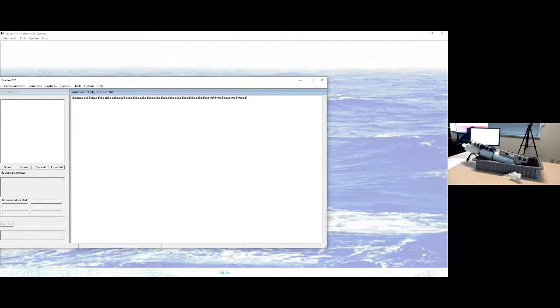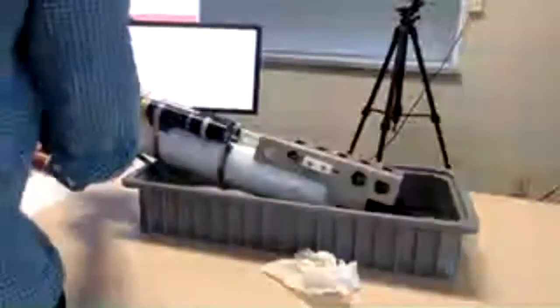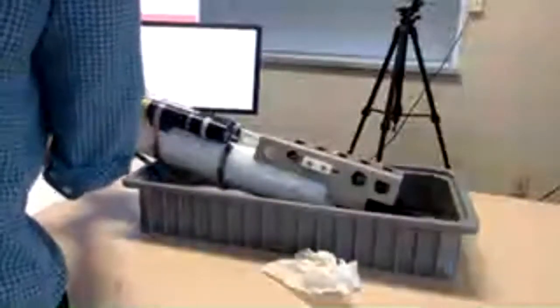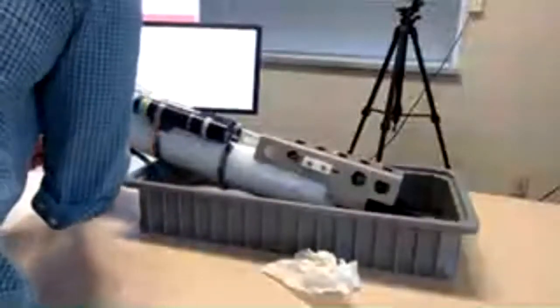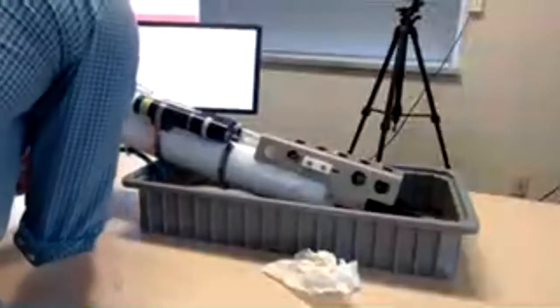At that point, I would recommend applying external power to your CTD. It's possible it's not talking because the batteries are dead or there are no batteries installed in the instrument. And then also troubleshoot, make sure that your data I/O cable is plugged into the right spot on your CTD's connector. And also make sure that you're connecting to your CTD at the proper baud rate.